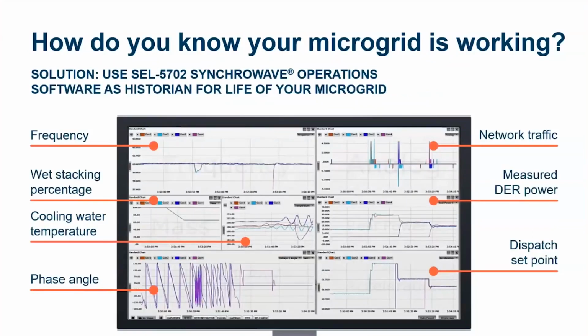Now, how do you know your microgrid's working? This is a similar question I asked before, but from a different perspective. What does working mean to you? Here on SYNCHROWAVE Operation, you see we track frequency of multiple generators. You can see some of the frequencies aren't the same. This means that that generator is actually decoupled from the grid. That means it's not participating. That's obvious with the eye. We can see that there's a thermostat that's cycling differently because the cooling water jacket on one machine is behaving differently than the others. Sounds like a call to maintenance to pull that machine out and change that $30 part.